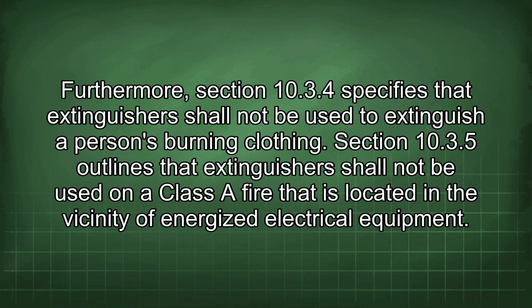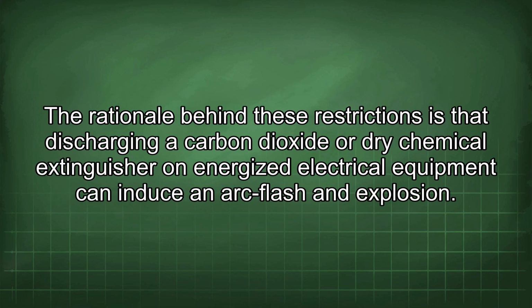Section 10.3.5 outlines that extinguishers shall not be used on a Class A fire that is located in the vicinity of energized electrical equipment. The rationale behind these restrictions is that discharging a carbon dioxide or dry chemical extinguisher on energized electrical equipment can induce an arc flash and explosion.